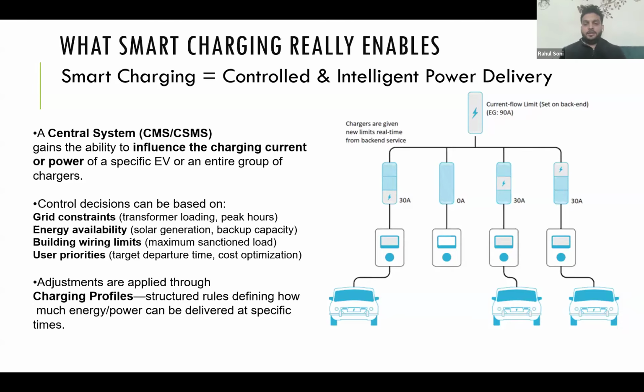In this diagram, you can see the total flow limit set on the back end is 90 ampere, but there are 4 chargers, each of which can charge at a maximum capacity of 30 ampere. All these limits are provided by the CMS through the software and communication protocol, in real time.